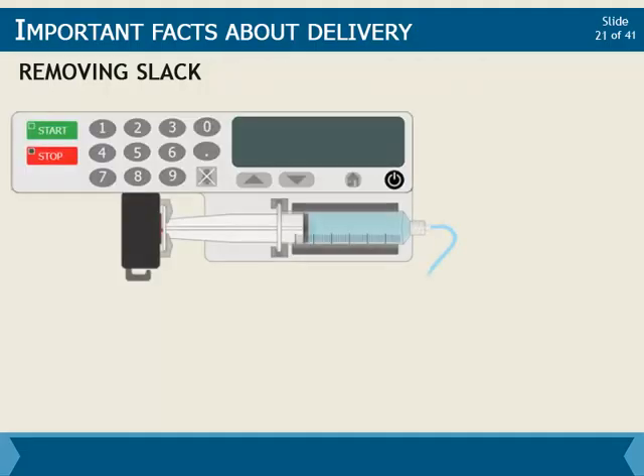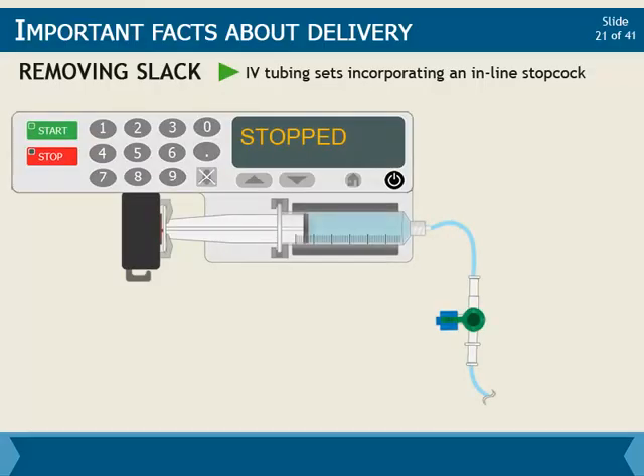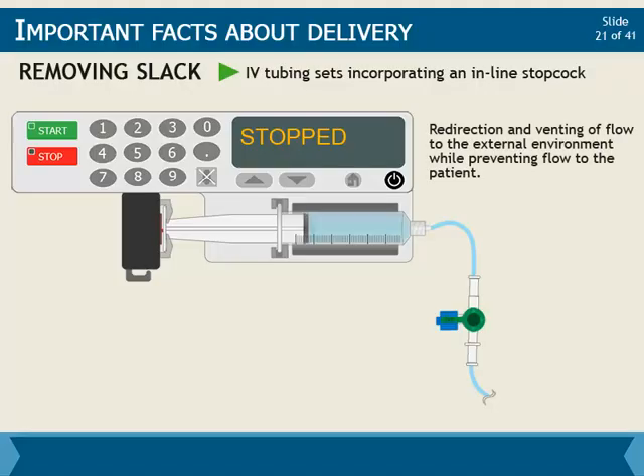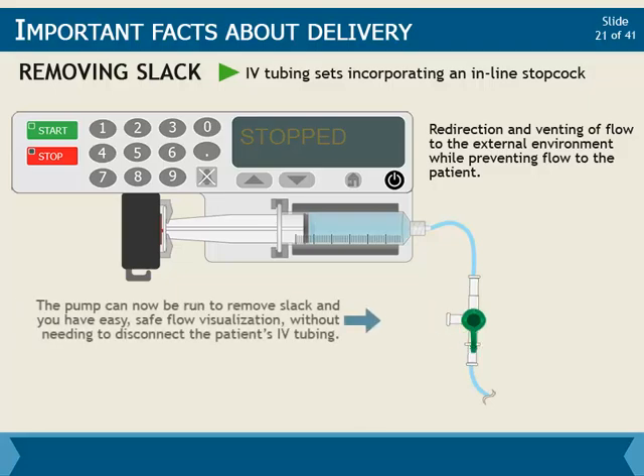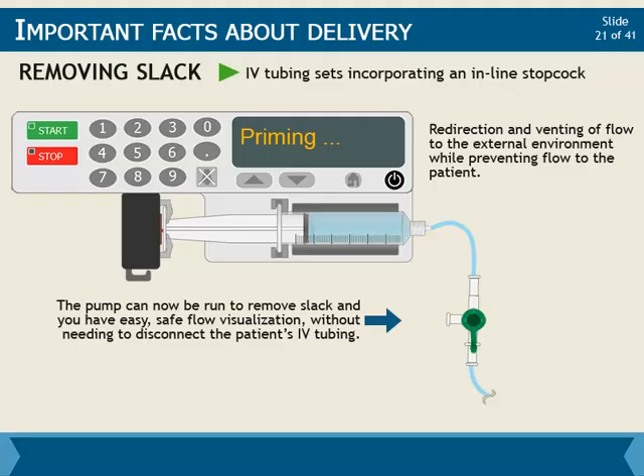In order to assist with removing slack, one institution designed and implemented IV tubing sets incorporating an inline stopcock near to where the tubing attaches to the syringe. When priming on the pump, this design allows for the redirection and venting of flow to the external environment while preventing flow to the patient. The benefit is that the pump can now be run to remove slack, and you have easy, safe flow visualization without needing to disconnect the patient's IV tubing. During the few seconds in which the inline stopcock is open to the air for flow visualization, it is essential to maintain aseptic technique.